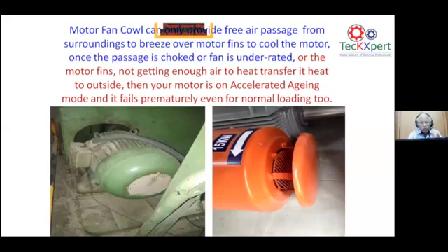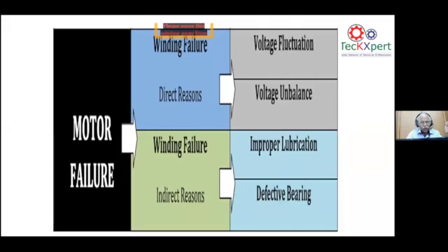All the motor OEMs give an excess number of fins, especially in IE3 motors and above, so that the motor heat is definitely dissipated outside to the ambient surroundings. So if the fan is not functioning on a TEFC motor, or the airflow is not there, definitely this is also affecting us. So motor failure has two aspects. One is the direct reason, the winding failure; the other is the indirect reason, which also ends in winding failure. The direct reason comes from the voltage fluctuation on the one side and the voltage unbalance on the other side.